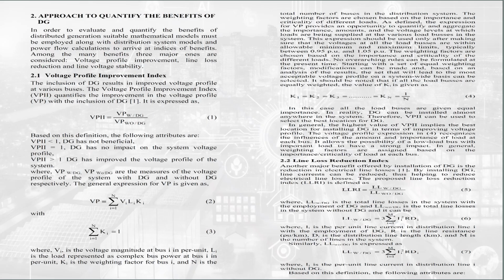Another important benefit is the reduction of losses in power lines. By installing DG, line currents can be reduced, thus helping to improve LLRI. Based on its definition, the following attributes are: if LLRI is less than 1, DG reduced electrical line losses. If LLRI is equal to 1, DG has no impact on system line losses. If LLRI is greater than 1, DG has caused more electrical line losses. This index can be used to identify the best location to install DG. The minimum value of LLRI corresponds to the best DG location scenario in terms of line loss reduction.